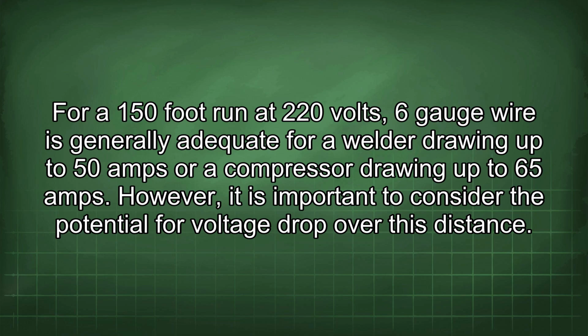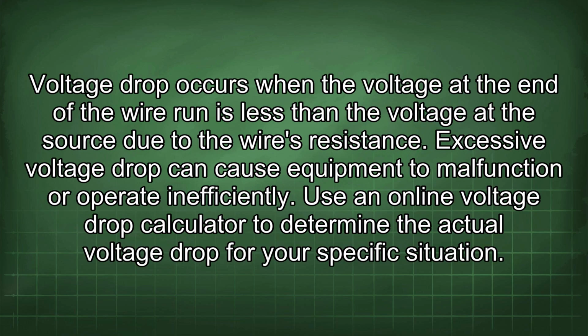However, it is important to consider the potential for voltage drop over this distance. Voltage drop occurs when the voltage at the end of the wire run is less than the voltage at the source due to the wire's resistance. Excessive voltage drop can cause equipment to malfunction or operate inefficiently. Use an online voltage drop calculator to determine the actual voltage drop for your specific situation.